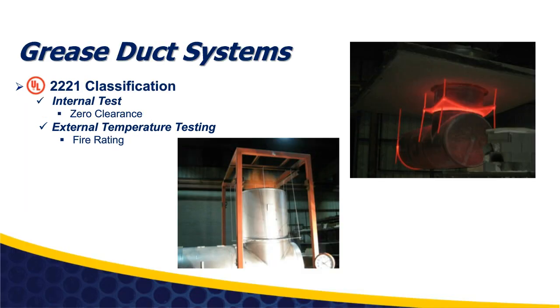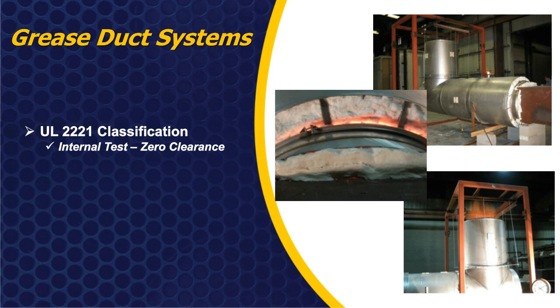Now, to have a fire rating of a product or to obtain zero clearance, a product would need to go through a UL 2221 classification. So for zero clearance, again, we go through an internal temperature test, and to receive a fire rating, you would go through an external testing of the product itself. On the internal test, you're basically going to subject your grease duct to temperatures equivalent to a severe grease duct fire and hold that temperature for a set amount of time while the outer shell is being measured for proper temperatures for clearance to combustibles.